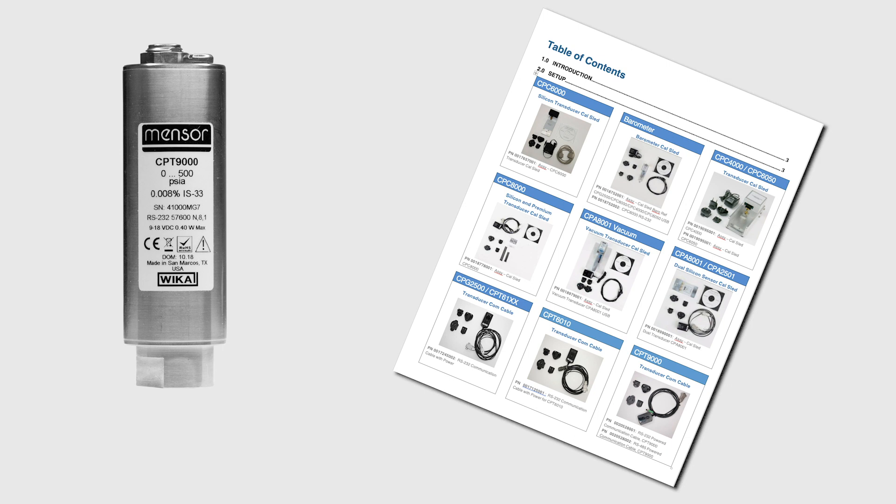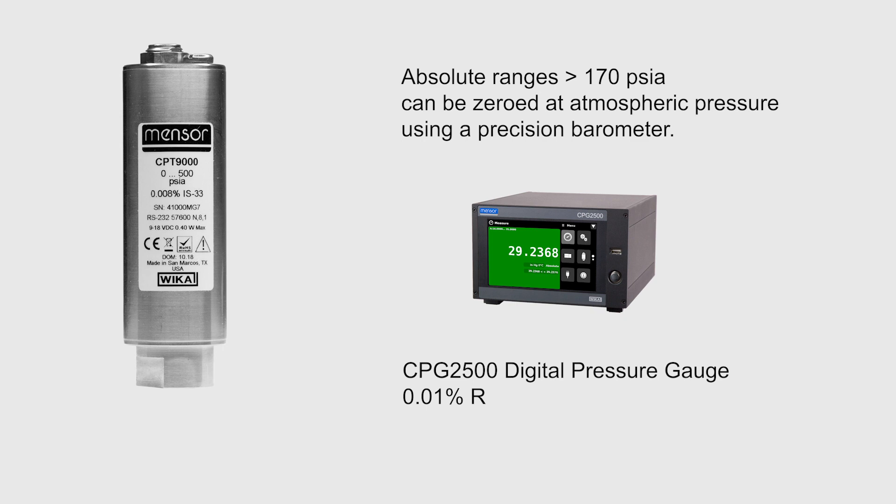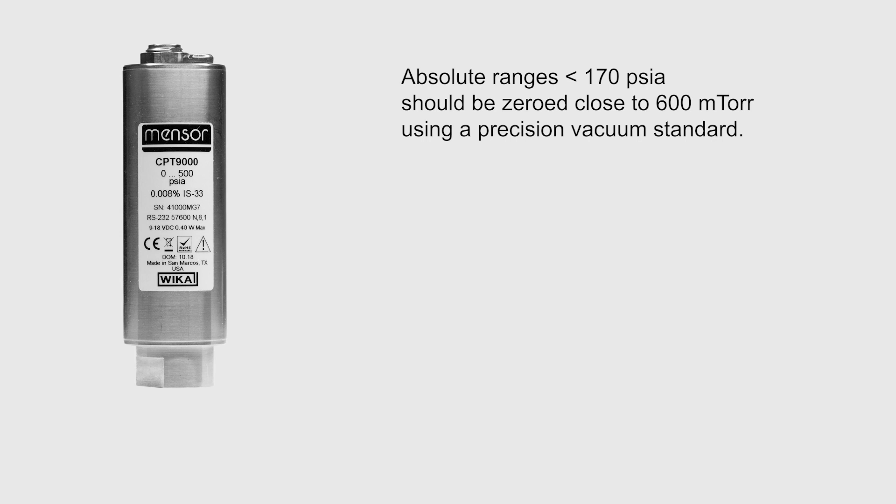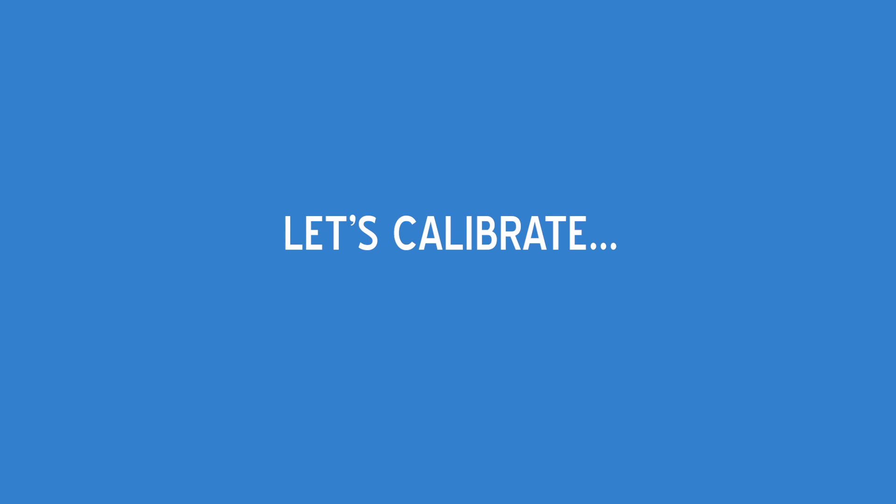Absolute ranges above 170 PSIA can be zeroed at atmospheric pressure using a precision barometer with an accuracy of 0.01% of reading. Ranges below 170 should be zeroed close to 600 millitorr using a precision vacuum standard. Alternatively, a gauge transducer can be easily zeroed by venting the pressure and reference ports to ambient pressure.